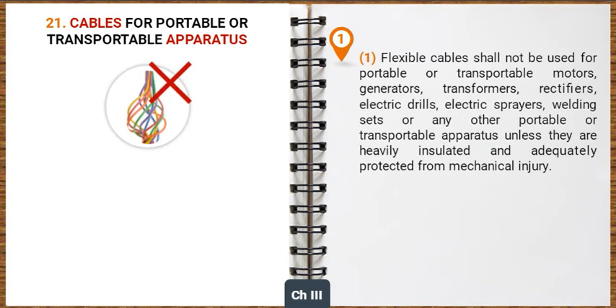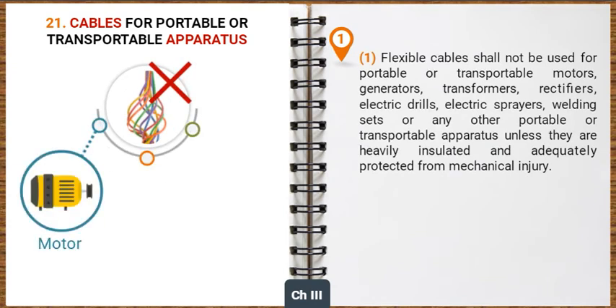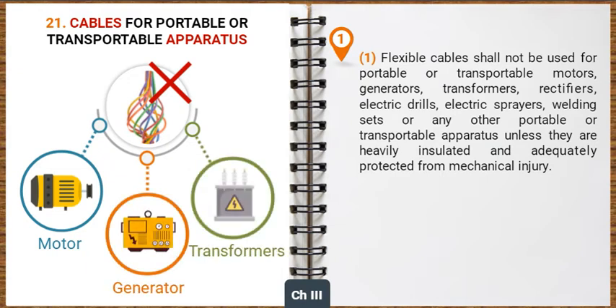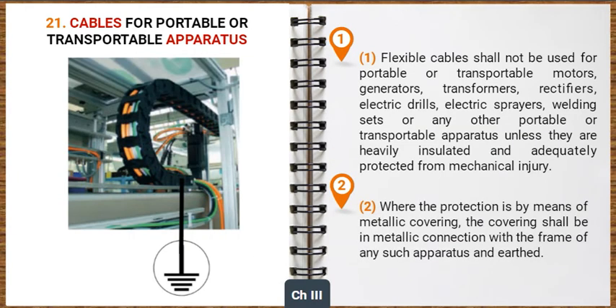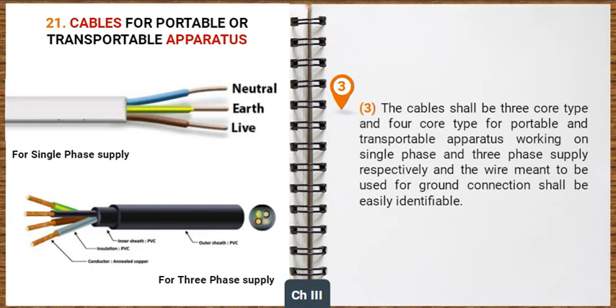Now let's learn about the general safety requirements for cables for portable or transportable apparatus. Flexible cables shall not be used for portable or transportable motors, generators, transformers, rectifiers, electric drills, electric sprayers, welding sets or any other portable or transportable apparatus unless they are heavily insulated and adequately protected from mechanical injury. Where the protection is by means of metallic covering, the covering shall be in metallic connection with the frame of any such apparatus and earthed. The cables shall be three-core type and four-core type for portable and transportable apparatus working on single-phase and three-phase supply respectively, and the wire meant to be used for ground connection shall be easily identifiable.